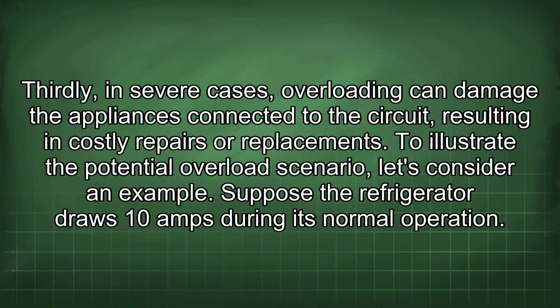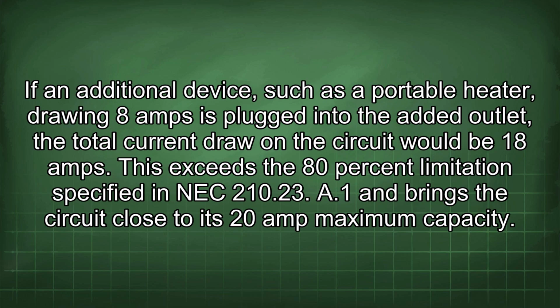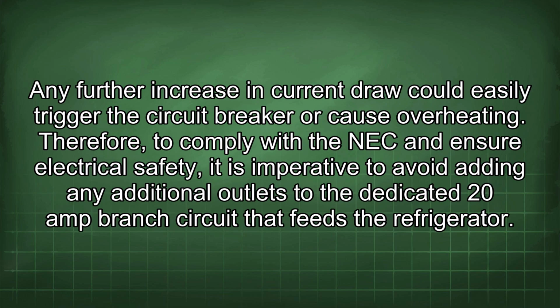Suppose the refrigerator draws 10 amps during its normal operation. If an additional device, such as a portable heater, drawing 8 amps is plugged into the added outlet, the total current draw on the circuit would be 18 amps. This exceeds the 80% limitation specified in NEC 210.23, A1 and brings the circuit close to its 20 amp maximum capacity. Any further increase in current draw could easily trigger the circuit breaker or cause overheating.